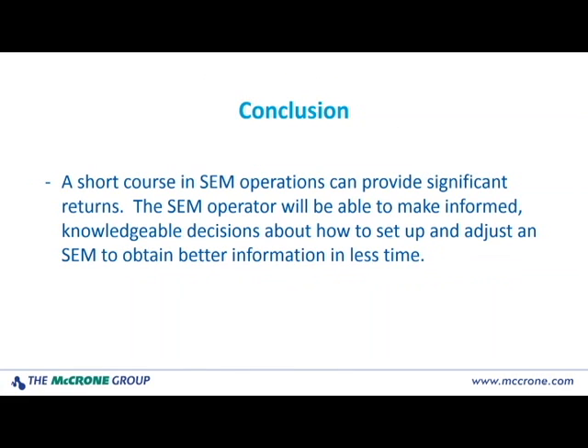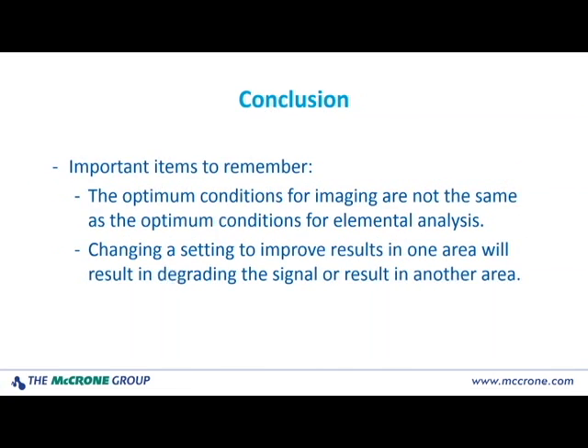Significant returns: the SEM operator will be able to make informed, knowledgeable decisions about how to set up and adjust your SEM to obtain better information in less time. You also have an operator that's no longer frustrated — there will be a much happier worker. A couple of important items to remember: the optimum conditions for imaging are not necessarily the same as the optimum conditions for elemental analysis. Often the two can be contradictory — we need high kV for one, low kV for another; high spot size for one, low spot size for another. Also, changing any one setting to improve a result in one area will certainly change the result or degrade the signal in another area.